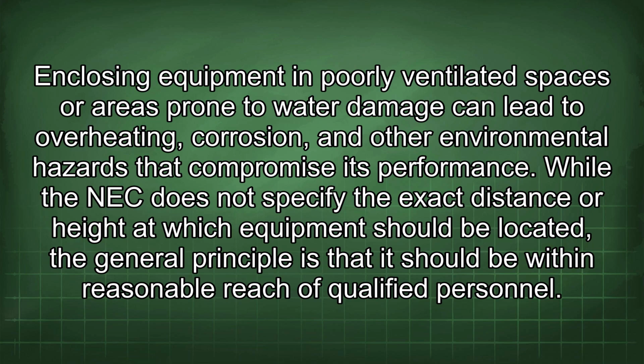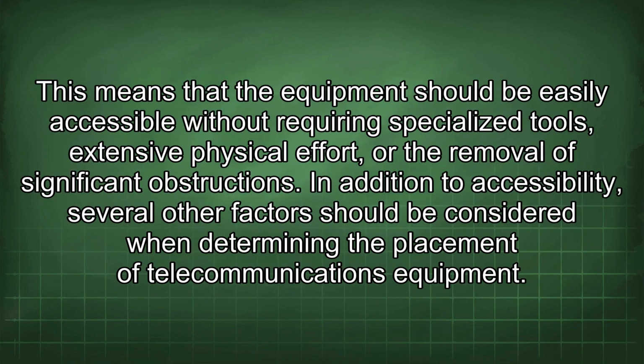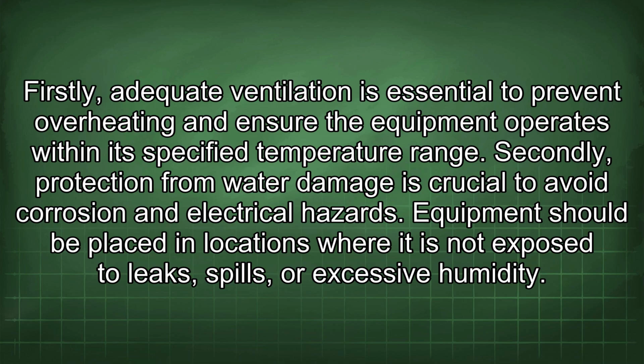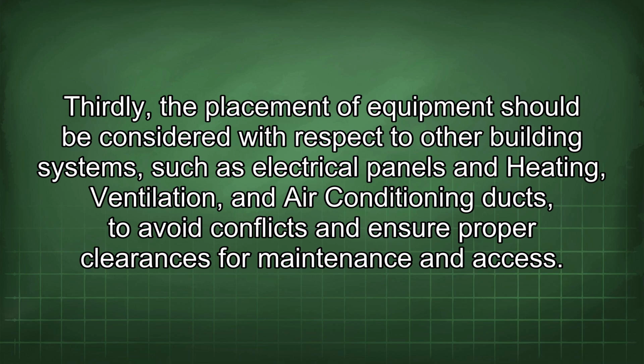While the NEC does not specify the exact distance or height at which equipment should be located, the general principle is that it should be within reasonable reach of qualified personnel. This means that the equipment should be easily accessible without requiring specialized tools, extensive physical effort, or the removal of significant obstructions. In addition to accessibility, several other factors should be considered when determining the placement of telecommunications equipment. Firstly, adequate ventilation is essential to prevent overheating and ensure the equipment operates within a specified temperature range. Secondly, protection from water damage is crucial to avoid corrosion and electrical hazards. Equipment should be placed in locations where it is not exposed to leaks, spills, or excessive humidity. Thirdly, the placement of equipment should be considered with respect to other building systems such as electrical panels and heating, ventilation, and air conditioning ducts to avoid conflicts and ensure proper clearances for maintenance and access.